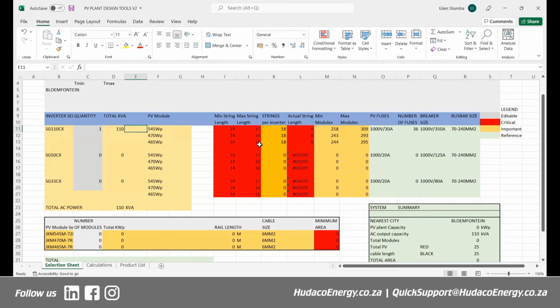So it shows you that 14 to 17 panels per string, multiplied by the number of strings the inverter can take, amounts to 258 up to 309 panels. So it's giving you an idea that for that inverter, if you're using 545 watt peak panels, you'll only require not less than 258 and not more than 309 panels. It's a range that makes your life easy for the design.